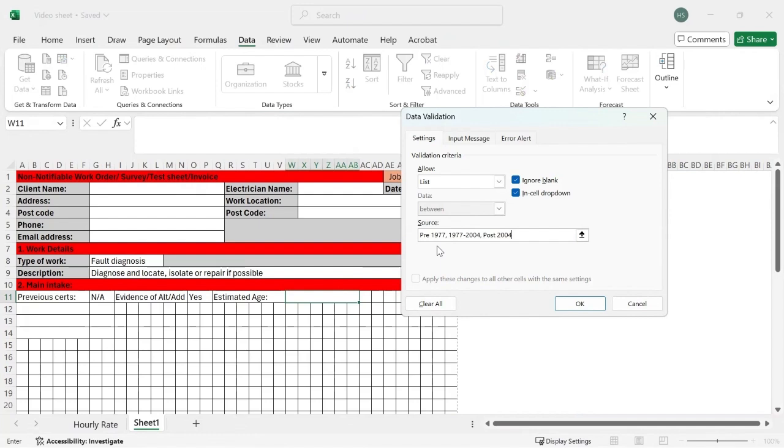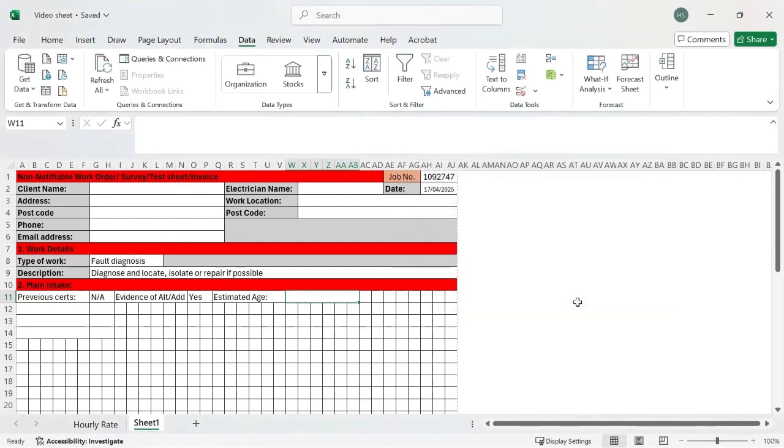If the whole thing's tripping and it's pre-1977, there's a good chance the whole thing's just really, really old. Maybe between 1977 and 2004 there were fewer RCDs back then, and so tripping may be more localized. Post 2004 is a good chance we've got a few different things going on. Anyway, there's just a simple way of aging the property.